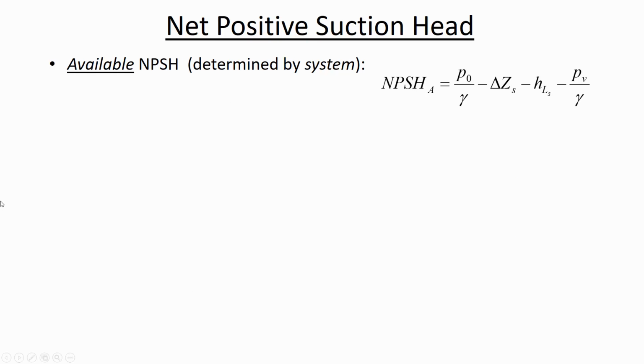So here's how you calculate how far away you are from having cavitation as a problem. The available net positive suction head is determined by the system curve. What you start off with, this first term, is related to the atmospheric pressure. And then all the other terms are decreasing how much head is available. So the delta Z_S is the elevation difference between the reservoir and the pump itself. H_LS is the head loss in the suction side of the pipe, so the water that goes from the reservoir just until it gets to the pump. And then P_V is the vapor pressure. And so the bigger this number, the further away you are from cavitating.